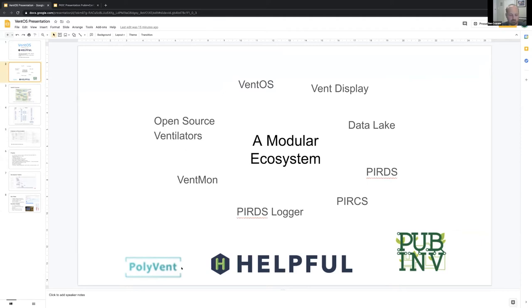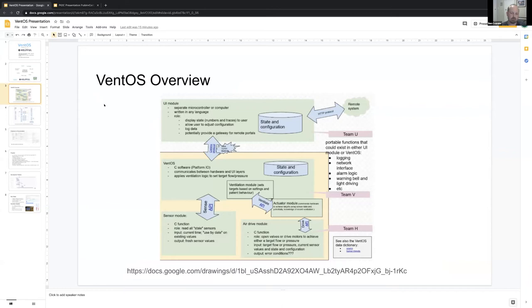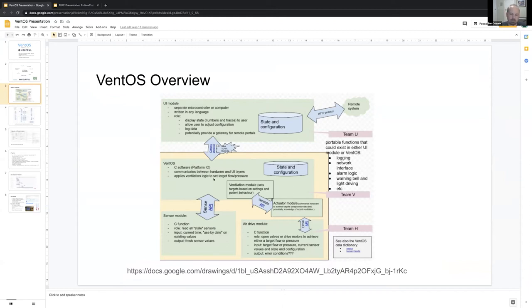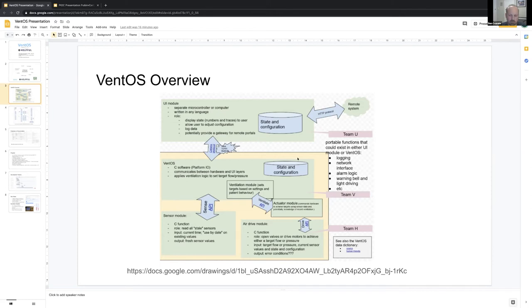We've really been partnering with a team called PolyVent, which is based in Germany, and have been working with their hardware. We don't build hardware—we are only focusing on the software component, which can be used with basically any type of ventilator, whether it's a bag squeezer, a blower motor, or valves, different types of microcontrollers, and also different displays as well. We're really trying to be as flexible as possible. We've broken it down into the core control system and then different sensor modules, an air drive module, and we're starting to work on a UI module. Those are the main four components, and we can break them up into maybe three or four different teams.